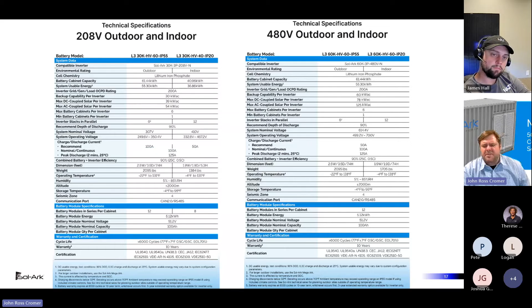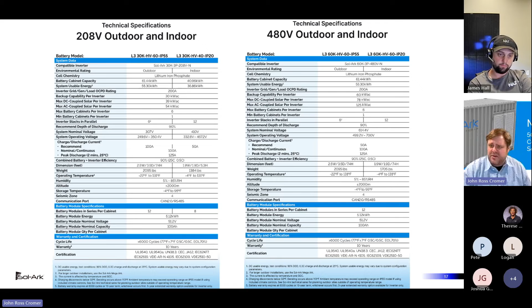These batteries have 10-year warranties. Some specs are changing. We've confirmed the altitude rating actually goes up to 3,000 meters rather than 2,000, so some small items like that. We always debate whether to put Fahrenheit or Celsius on the data sheet, and sometimes you make one decision, it comes back, and you have to switch to the other. But other than going from 12 battery cabinets to 16 for indoor use, and that altitude change up to 3,000 meters, everything else here should stay the same.